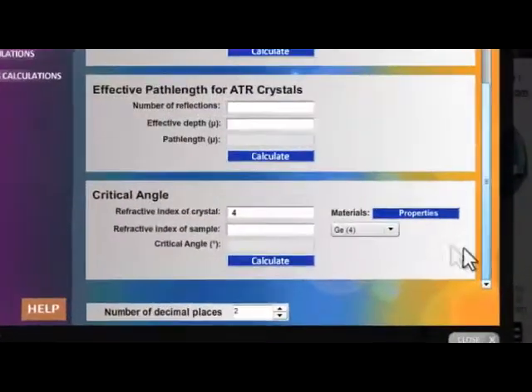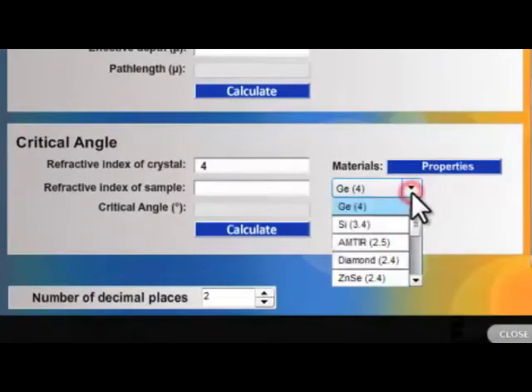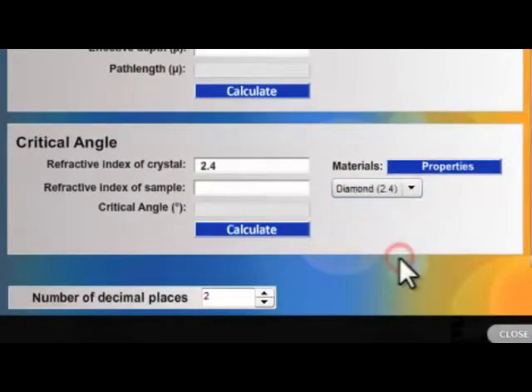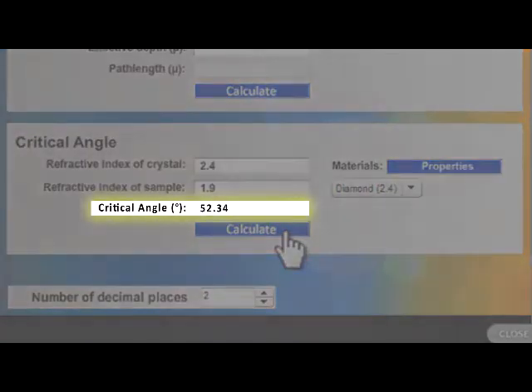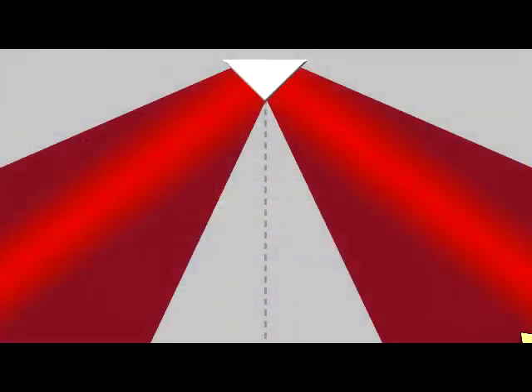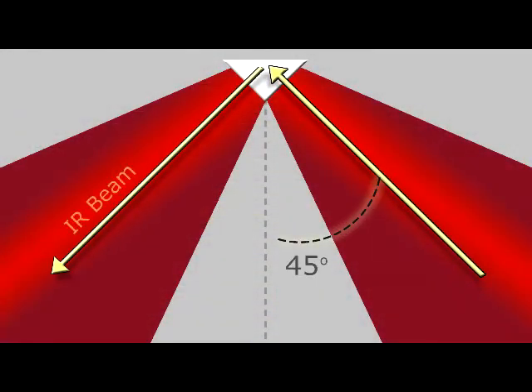In this example, we'll use the Gladiator Diamond ATR. Select the crystal and enter 1.9 for the refractive index of the sample. The critical angle is 52 degrees, which is greater than the accessory's angle of incidence of 45.